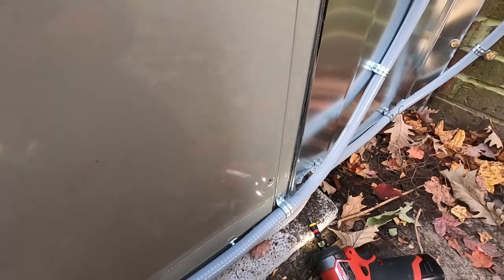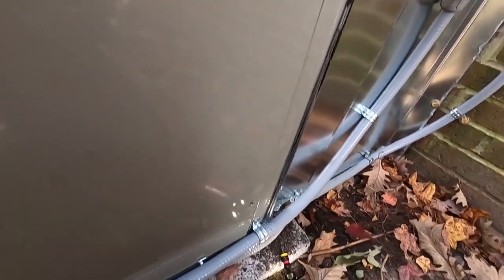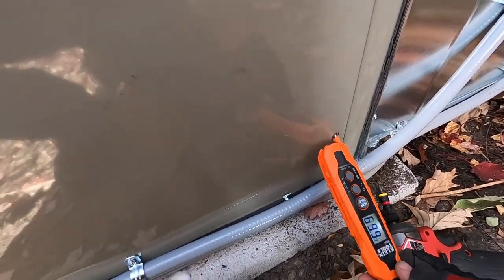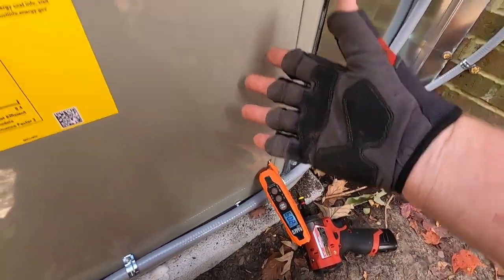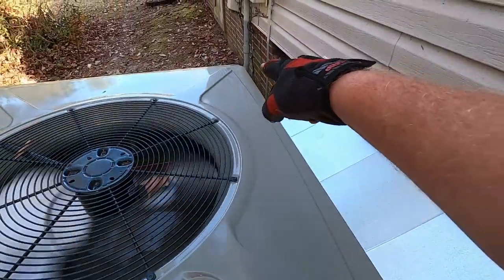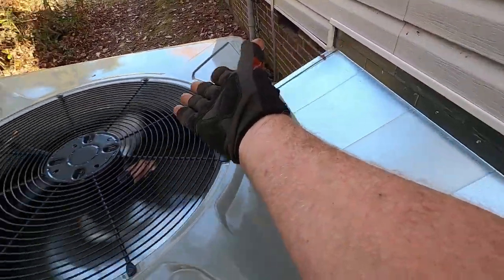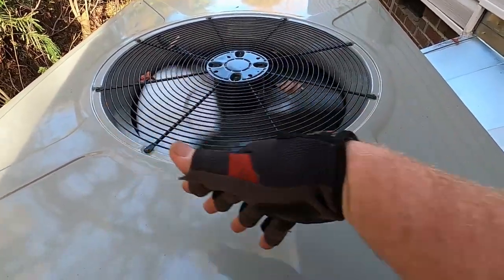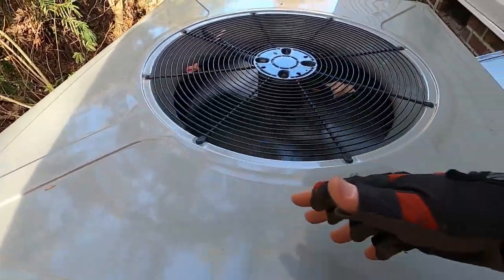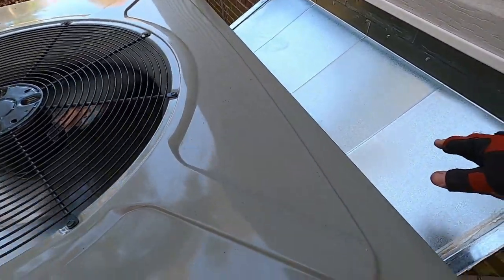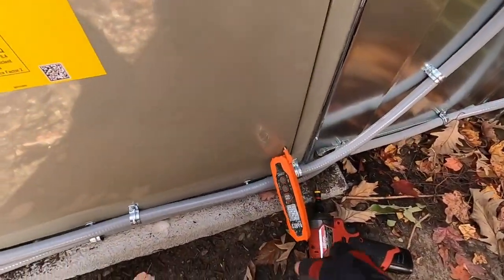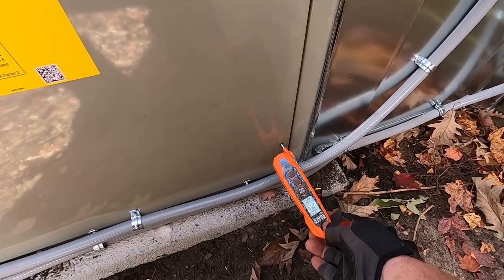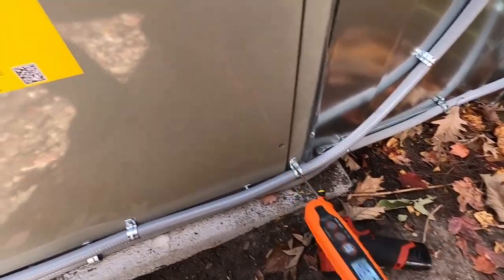And usually on these package units, I'll come over here and pop one of these screws out. Slide that probe in there. On this particular unit, this is the supply side. That's going to be your return side, so your return's coming in here, going through the system, through the coil, the gas, heat exchanger, heat strips, whatever it's set up, and your supply is feeding back through here. So I'll come down here on this side panel, and we're getting about a 47 degree supply right there.